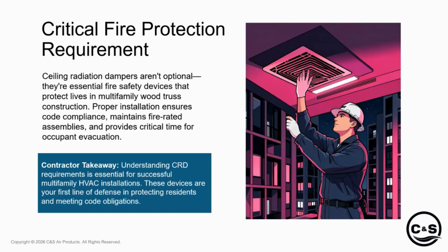Steve asked, is this also usable in extremely hot areas like California? Yes, oh yeah. The temperature outside doesn't really have much to do with the requirement from UL on the inside. You could be in one of the coldest markets in the U.S., like Minnesota, and the fire protection requirements are still the same in any part of the U.S. Really the only thing that changes market to market is whether you want an insulated or uninsulated ceiling radiation damper. Brent can probably speak more to the uninsulated side up north, since a lot of my territory is towards the insulated areas of the U.S. But the requirements are still the same. Does that answer your question?